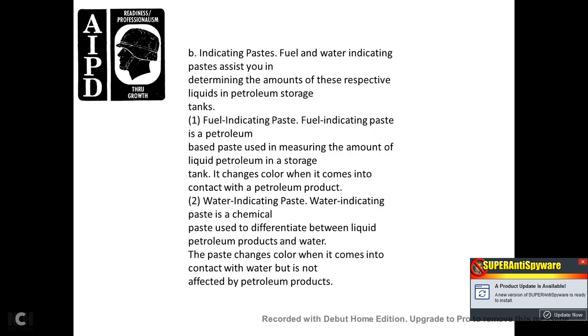12. Indicating paste. Fuel and water indicating paste is used to determine the amount of the respective liquid in petroleum storage tanks. Fuel indicating paste is a petroleum-based paste used to measure the amount of liquid petroleum in a storage tank; it changes color when it comes in contact with the petroleum product. Water indicating paste is a chemical paste used to differentiate between liquid petroleum products and water; it changes color when it comes in contact with water but is not affected by petroleum products.